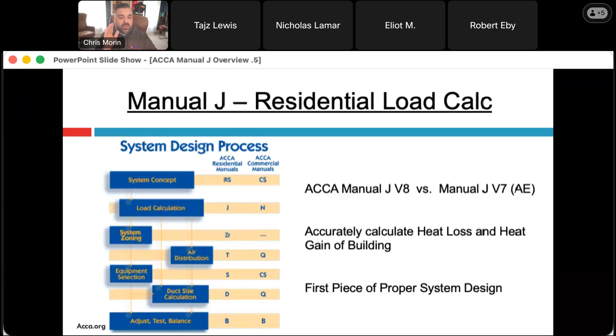So first off, the thing that impacts the heat loss the most, and probably the cooling gain significantly more than here in the Northeast, down in Austin, you have to use the outdoor design conditions based on Table 1A in ACCA Manual J. So in heating, that means your outside design temperature is 30 degrees. In cooling, if you use Table 1A out of ACCA Manual J, it's actually 98 degrees. And Austin Energy has a building code amendment to size to 100 degrees, not 98 degrees.